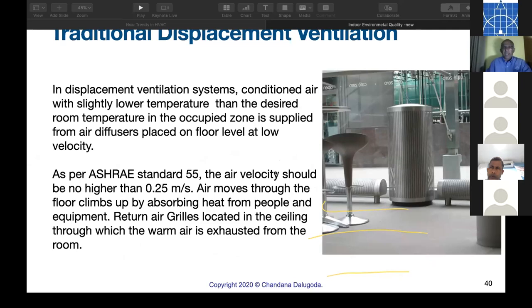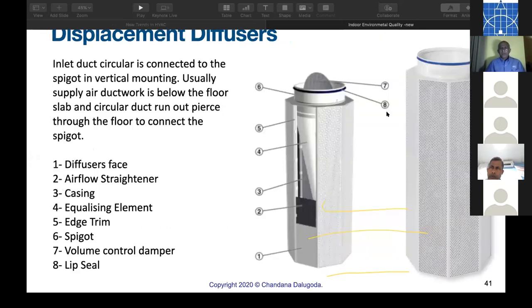As per ASHRAE Standard 55, the air velocity should be no higher than 0.25 meters per second. When you check, air is just flowing down. When you are closer to the grill, you don't even feel it. Very minute feeling, so it is dumping air downwards. Sometimes this grill is installed upside down, with the supply duct coming from the top. All the ductwork is below the floor, or, for above-floor diffusion, the ductwork goes above the ceiling.